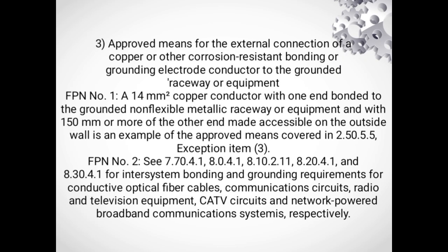Number 3. Approved means for the external connection of a copper or other corrosion-resistant bonding or grounding electrode conductor to the grounded raceway or equipment. For example, a 14 mm squared copper conductor with one end bonded to the grounded non-flexible metallic raceway or equipment and with 150 mm or more of the other end made accessible on the outside wall is an example of approved means covered in 2.50.5.5.